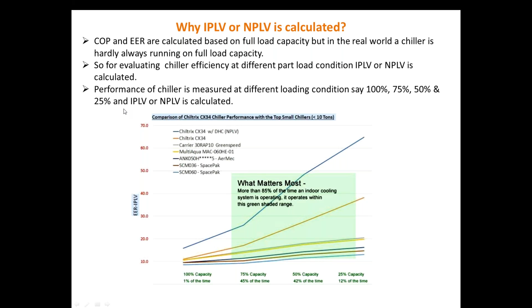Okay, so most of the time your HVAC devices or refrigeration devices work at part load performance. That's why IPLV or NPLV is calculated, and they take into account the part load performance of the refrigerating devices. So the performance of these refrigerating devices is measured at different loading conditions, say 100, 75, 50, and 25%. So, how do we calculate IPLV and NPLV?